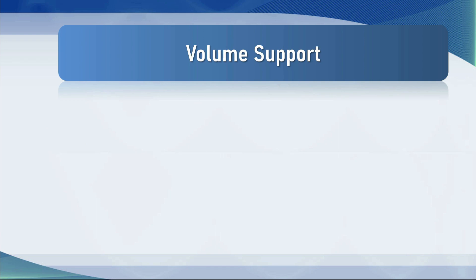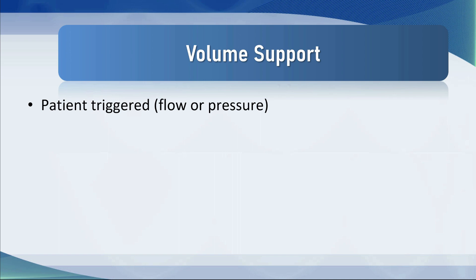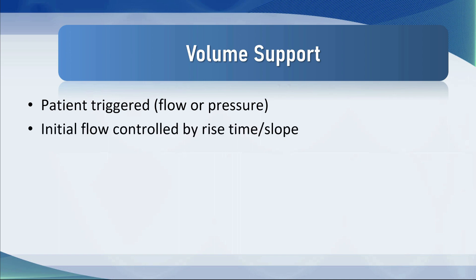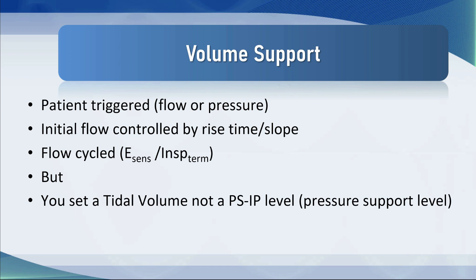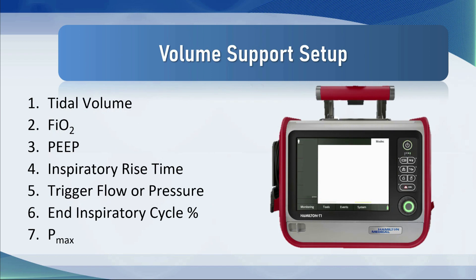Let's look at some of the key components of volume support. First, it's patient triggered — you'll use flow-by triggering or pressure triggering. The initial flow is controlled by the rise time or slope, just like pressure support. It's flow cycled using expiratory sensitivity, but you set a tidal volume, not a pressure support inspiratory pressure level. The pressure support is variable and determined by the ventilator — it's a closed loop system. When setting up the ventilator you set a tidal volume, an FiO2, a PEEP, a rise time, trigger flow or pressure, an end-inspiratory cycle percentage, and a Pmax.